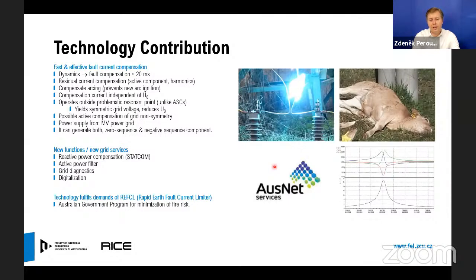The compensation current which we are generating has an arbitrary shape and is independent of zero sequence voltage. We are operating the device outside the problematic resonant point, which improves the symmetricity of the grid voltage and reduces the zero sequence component under trouble-free operation. We are able to actively compensate the grid non-symmetry. We are getting the power supply directly from the grid, so we can offer full standalone operation. And we are able to generate the positive sequence, zero sequence, as well as negative sequence components of the current.